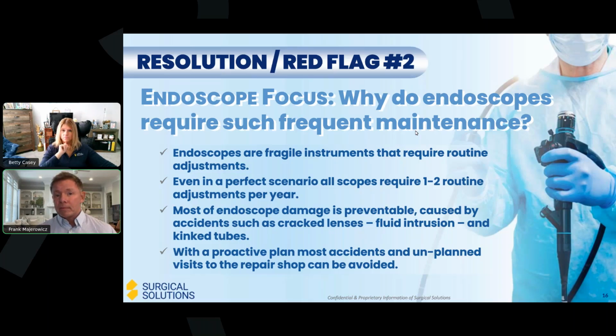So for that reason, you will always see your inventory of scopes, any given month, one or two may be going out for one of these routine adjustments, okay? However, to that point, most endoscope damage is preventable, okay? If I had to give you a ballpark scenario, I would say that 80% of the endoscopes that we get in for repair are preventable accidents, user-related damage, and only 15 to 20% would be those normal wear and tear items that just need to come in for an update.